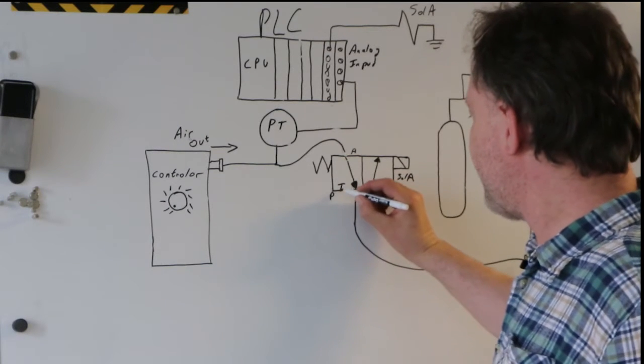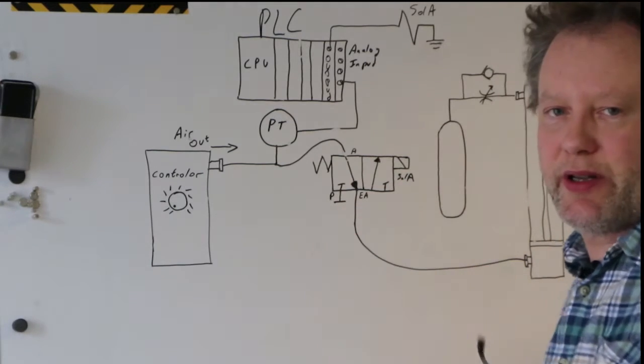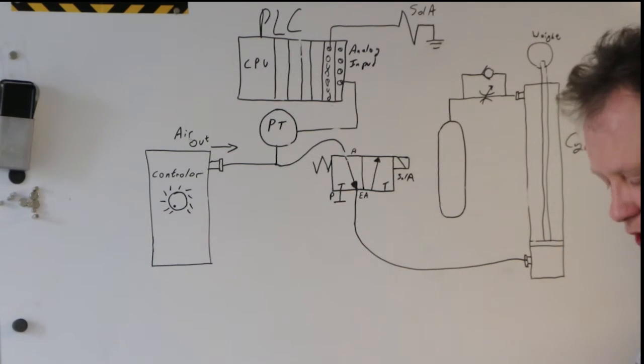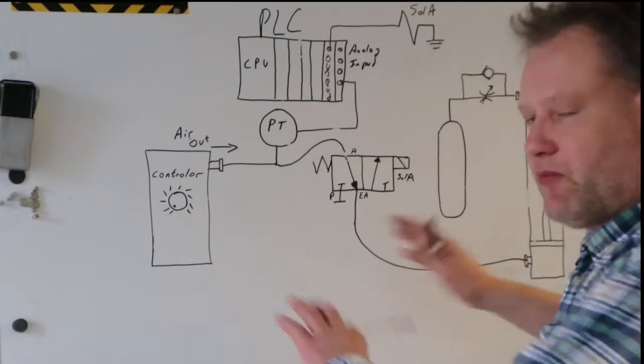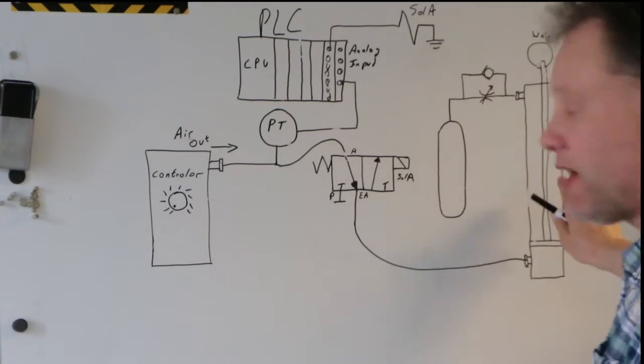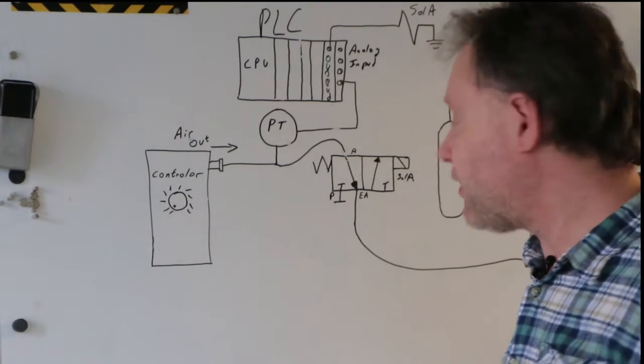Now, the other thing is, I put a T here, and you saw it. You saw that little plug there? I'm going to put a T there to simulate the plug. So, now, what's going to happen is that, if I don't energize it, the whole system works just fine. This guy can drive the muscle as long as it wants. At the beginning, at the end of the cycle, the PLC is going to energize the solenoid.